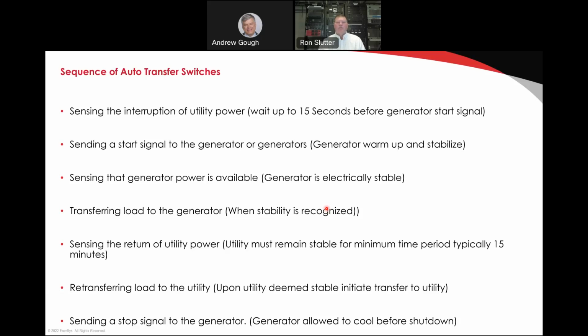Most generators, diesel generators specifically, have turbos. And if you are at a very high load on a diesel generator and you just shut it off after you had all this load on there, there's a good chance you're going to fry the oil in the turbo or boil the oil.